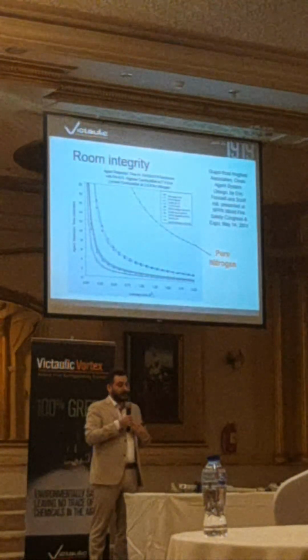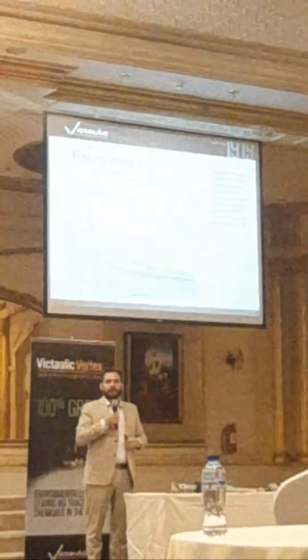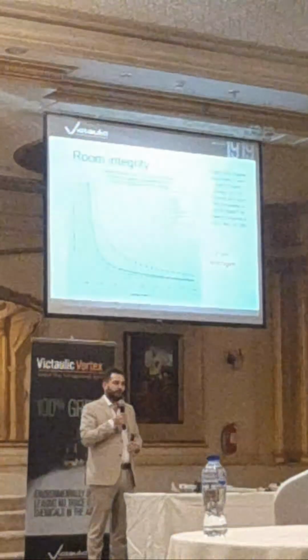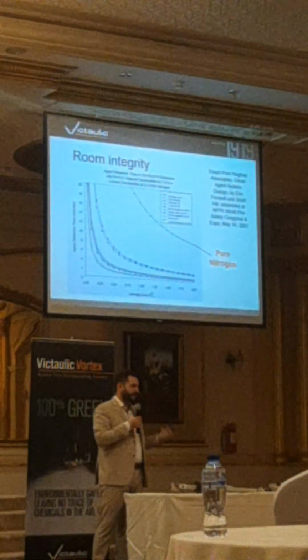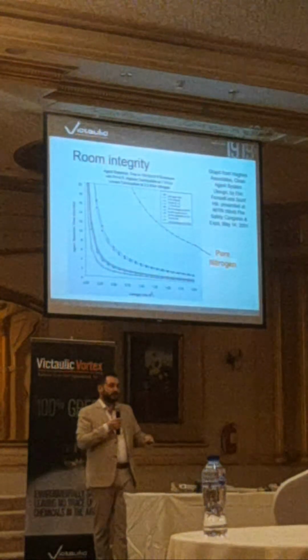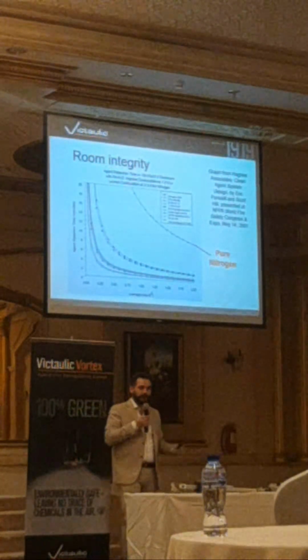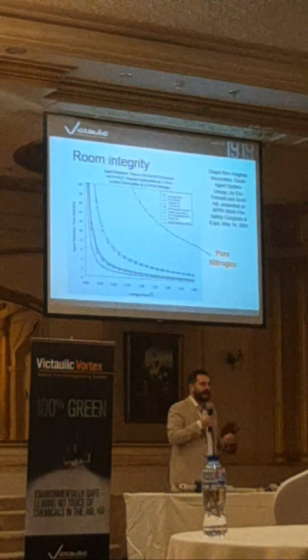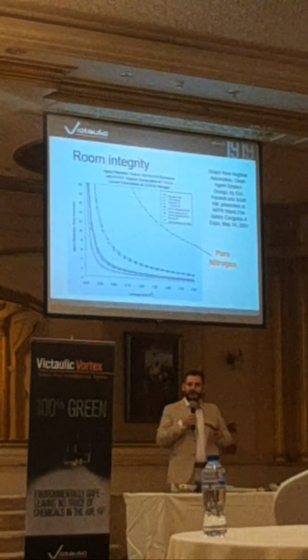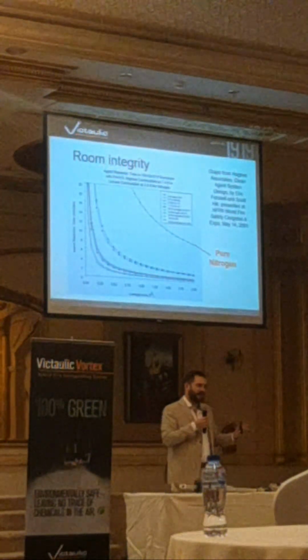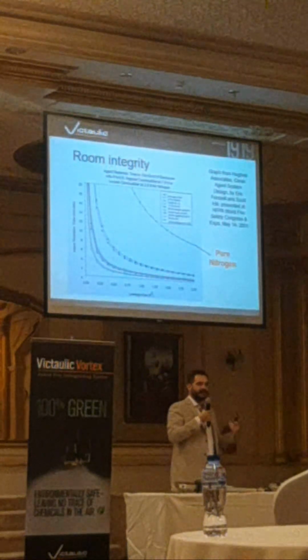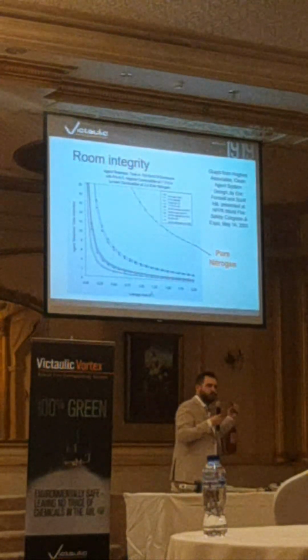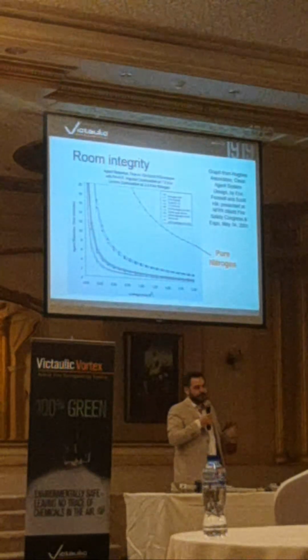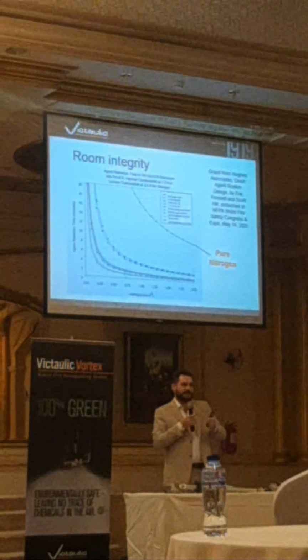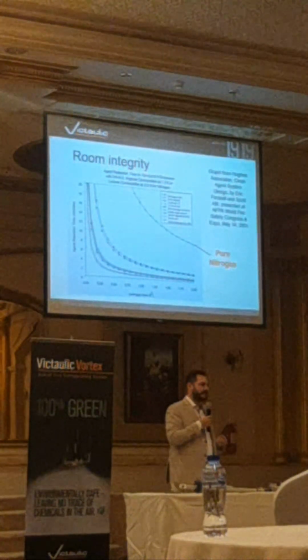If, however, you look at CO2 — luckily for us humans it's only parts per million in the air we breathe — doing a CO2 discharge means it's not only heavier, so it sinks to the bottom, but also because the concentration of CO2 in normal air is very low, once it sees an opening, it's gone. It tries to balance itself out as quickly as possible. The same happens with FM200. The better gases are the inert gases.